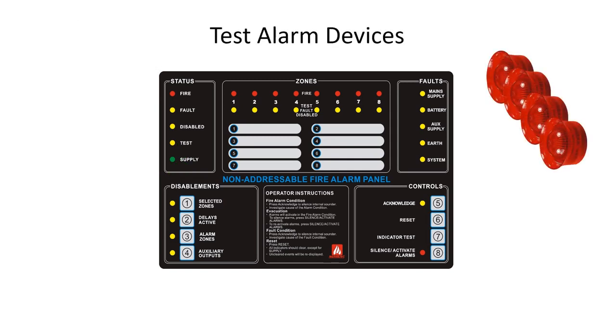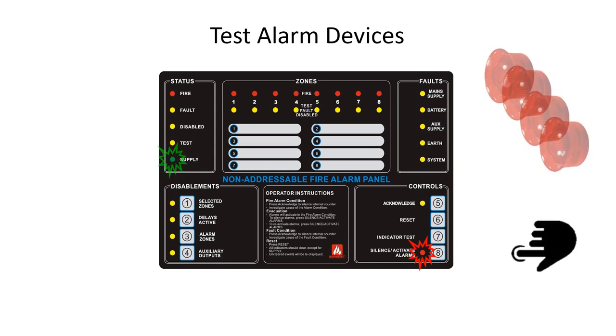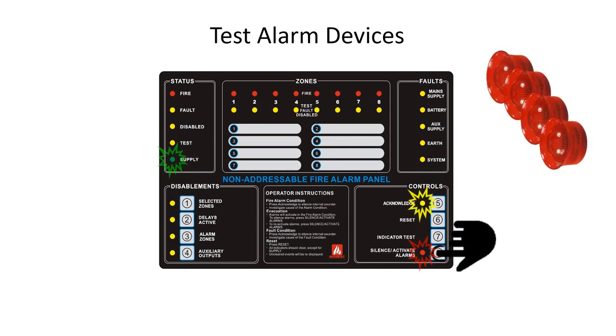To check the operation of the audio-visual alarm devices, enter Access Level 2 and press the Silence Activate Alarms button. The Silence Activate Alarms LED and the Acknowledge LED will flash. Press the Acknowledge button to confirm. The Acknowledge LED will be off, the Silence Activate Alarms LED will be on, and the audio-visual alarm devices will operate. To turn off the alarm devices, press the Silence Activate Alarms button.